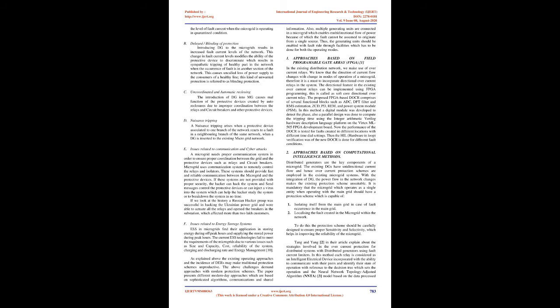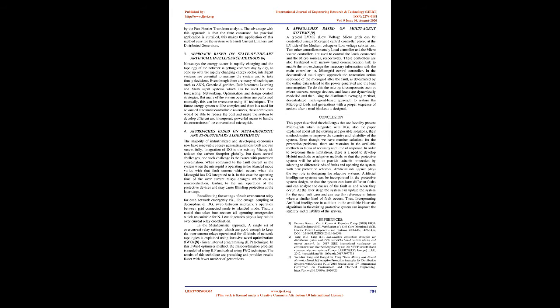Thus, the generating units should be enabled with fault ride-through facilities, which has to be done for both the operating modes. One approach is based on field programmable gate array, FPGA. In the existing distribution network, we make use of overcurrent relays. We know that the direction of current flow changes with the change in modes of operation of a microgrid, therefore it is a must to incorporate directional overcurrent relays in the system. The directional feature in the existing overcurrent relays can be implemented using FPGA programming. This is called a soft-core directional overcurrent relay.